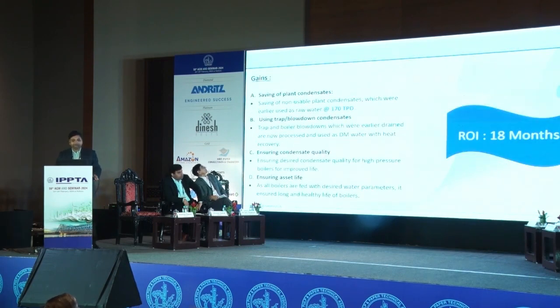With this, we will be able to save 170 tons of condensates which were earlier not utilized in the boilers and were being used as soft water or raw water. The trap and blowdown condensates are also now being recovered. The condensate quality is ensured and the asset life is also ensured. The ROI of this project was 18 months.